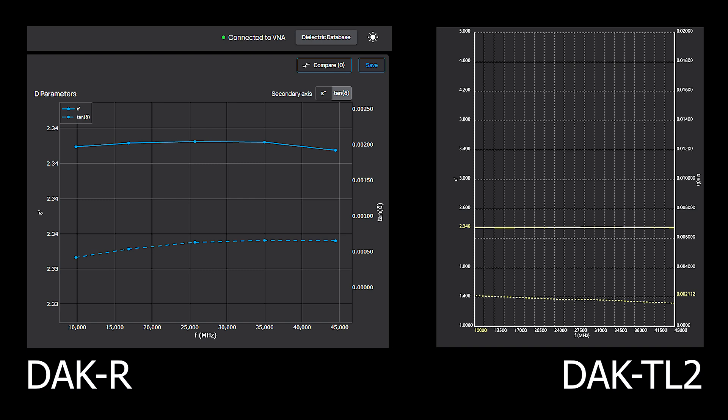As expected, loss measurements with DAK-R provide more accurate readings. I'm very happy to see that the DAK-TL2 and DAK-R measurements are in complete agreement with deviations well within the combined uncertainty of both methods.